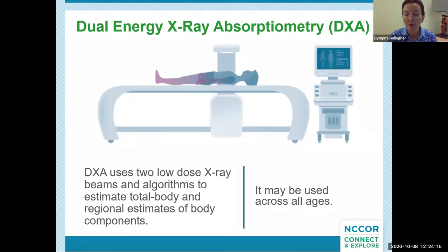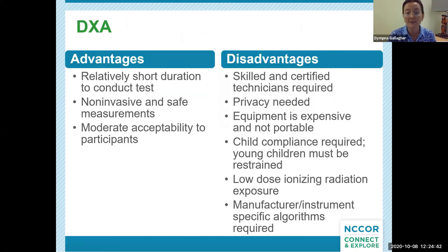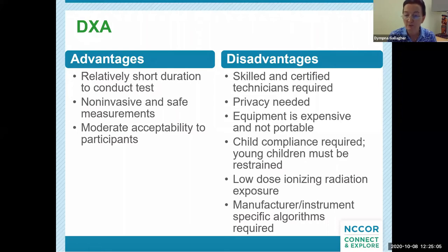Dual energy X-ray absorptiometry, or DEXA, uses two low-dose X-ray beams and instrument-specific algorithms to estimate total body and regional estimates of body components, including bone mineral content, bone-free fat-free mass, and fat mass. This method can be used across all ages from infancy through adulthood. Advantages include relatively short duration, non-invasive and safe, and moderate acceptability. Disadvantages include skilled and certified technicians required, privacy needed, equipment is expensive and not portable, young children must be restrained, low-dose ionizing radiation exposure is involved, and manufacturer instrument-specific algorithms are required.